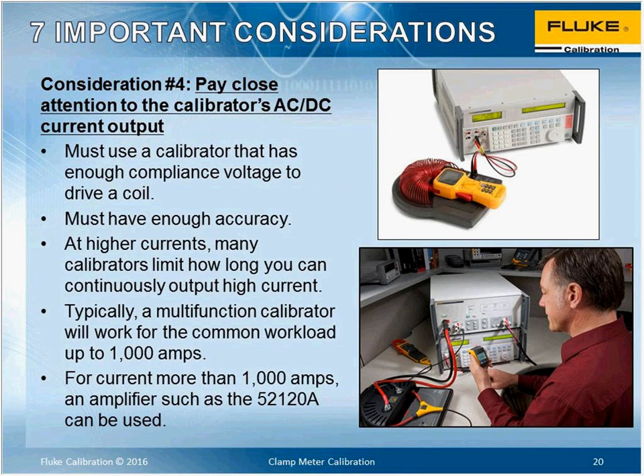Number 4, pay close attention to the calibrator's AC/DC current output. This is up there in terms of considerations as the accuracy. It's hard to explain in some cases, but basically, as current increases, no matter what product you use, and we're talking about a multi-product calibrator sourcing current, the longer you output high current, the more heat it generates, and that's basic physics with this electrical device. But what happens is thermal effects start hindering the measurement uncertainty, and also because sometimes you're driving into a coil, you're going to experience high inductive loads, which the calibrator needs what is called compliance voltage to be able to drive through that coil but maintain the accuracy stated.